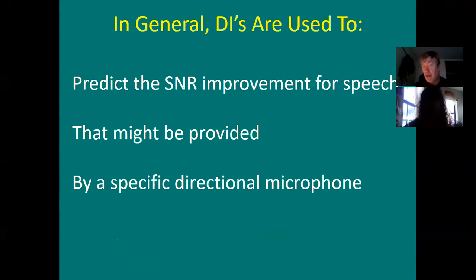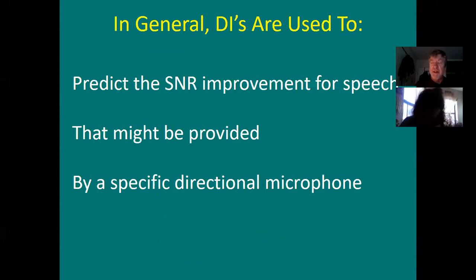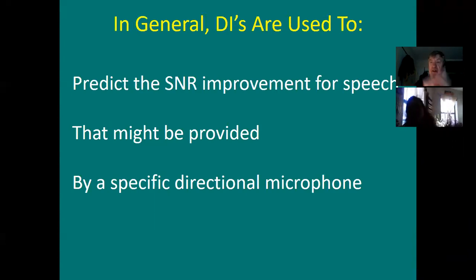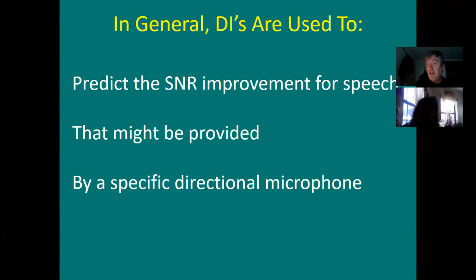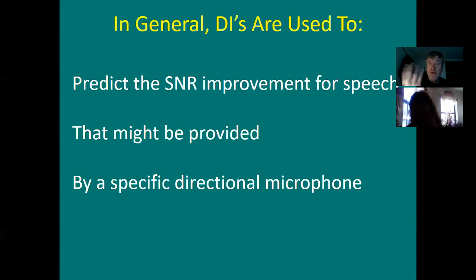Take the message home: you want to have good directionality for 500, 1000, 2000, and 4000 Hz. Directional indices are used to predict the signal-to-noise ratio improvement for speech provided by a specific directional mic. Chapter 9 in the textbook covers the benefits of directional mics versus digital noise reduction and puts it all together. Chapter 8 covers digital noise reduction, feedback reduction, and expansion.